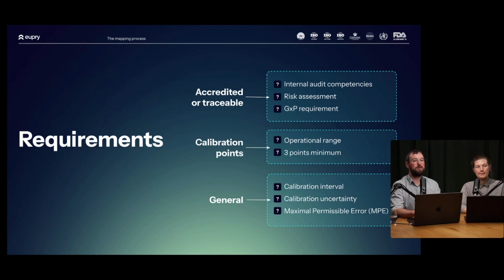Moving on, the second requirement you should set is what are your calibration points, and there you need to think about your operational range, and we'll go more into detail why that matters. But you need to assess, for the specific process in which you're going to use this equipment which is going to be calibrated, what is the operational range? So let's say you have a fridge that would typically be between 2 and 8 degrees Celsius. Well, can it go below?